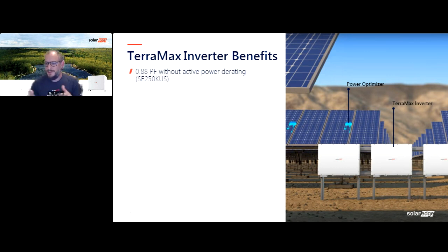And so when I do that, I'm limiting my active power. And active power is ultimately what you're getting paid for. That's how you're making your money on your dollars or cents per kilowatt hour produced. And so if I'm derating that, I'm losing money. I'm leaving money on the table. So our 250 kilowatt device is limited to 250 kilowatts of active power, but it has a 285 kVA apparent power rating, which allows you to take advantage of operating at a lower power factor without compromising on active power.